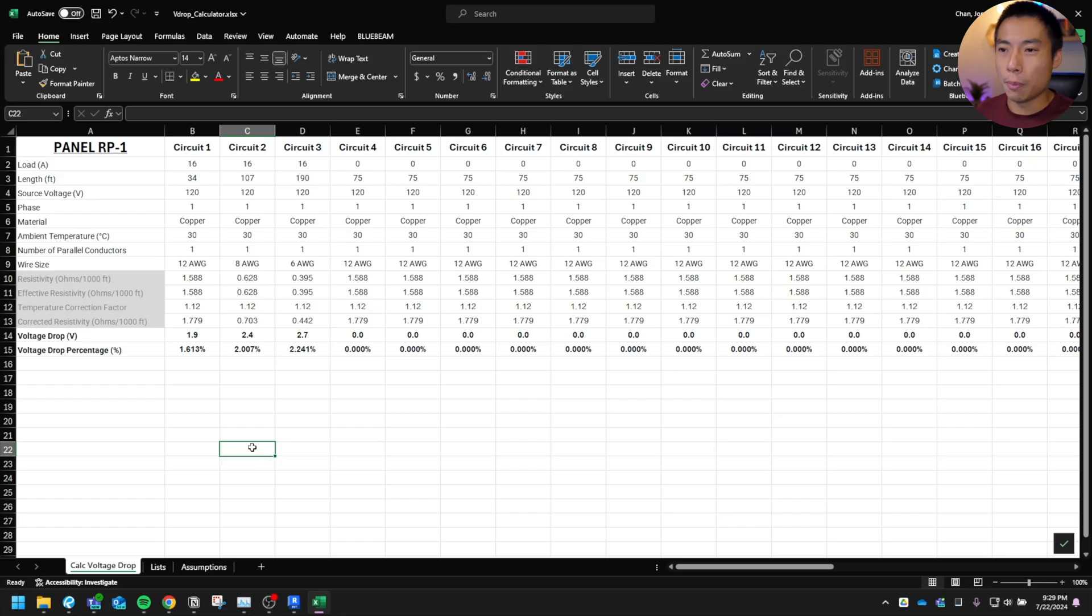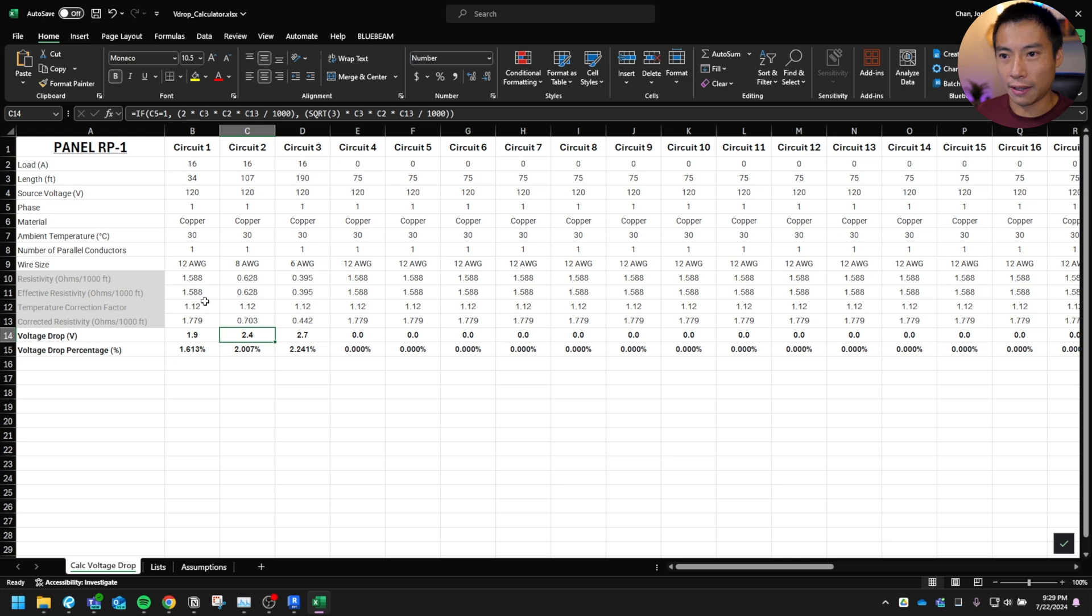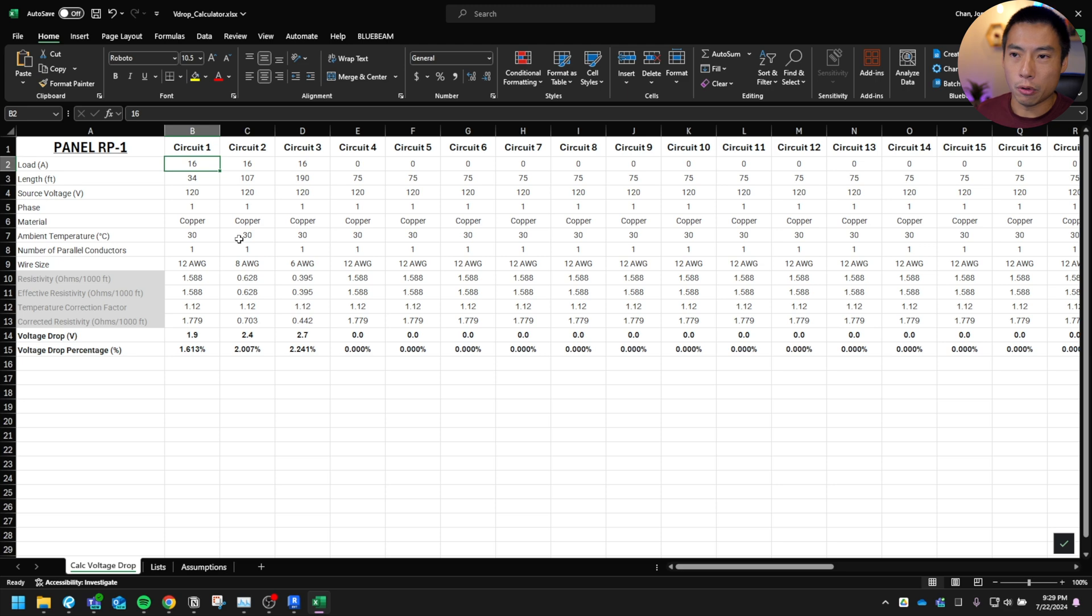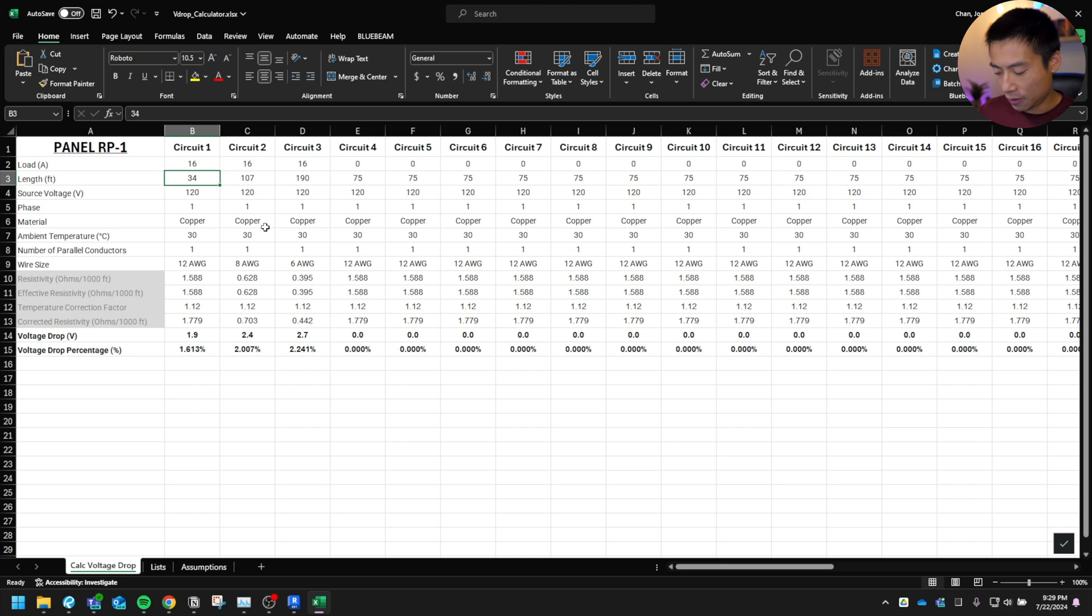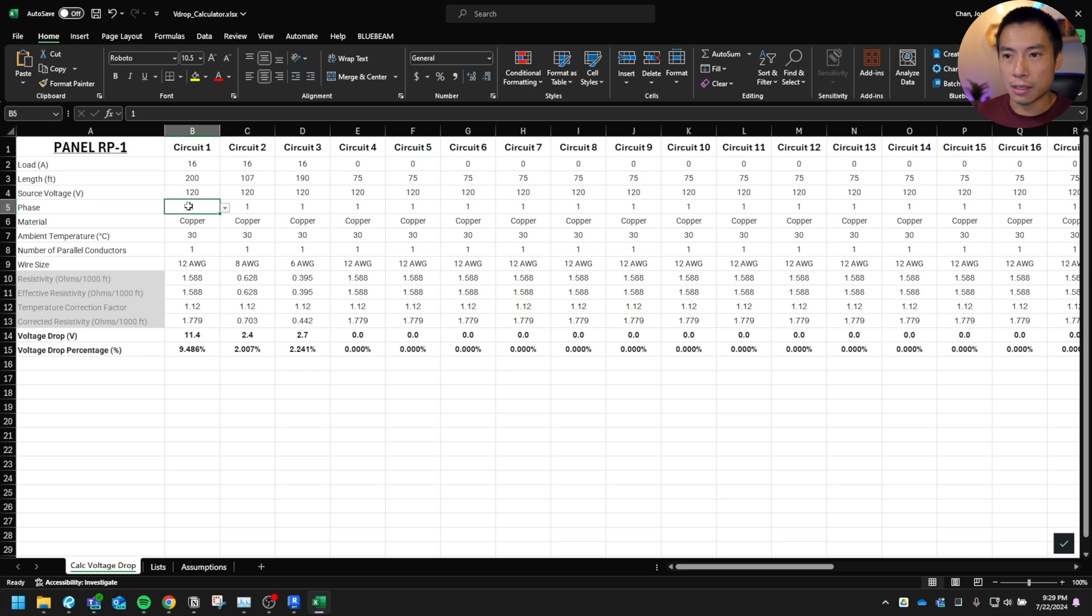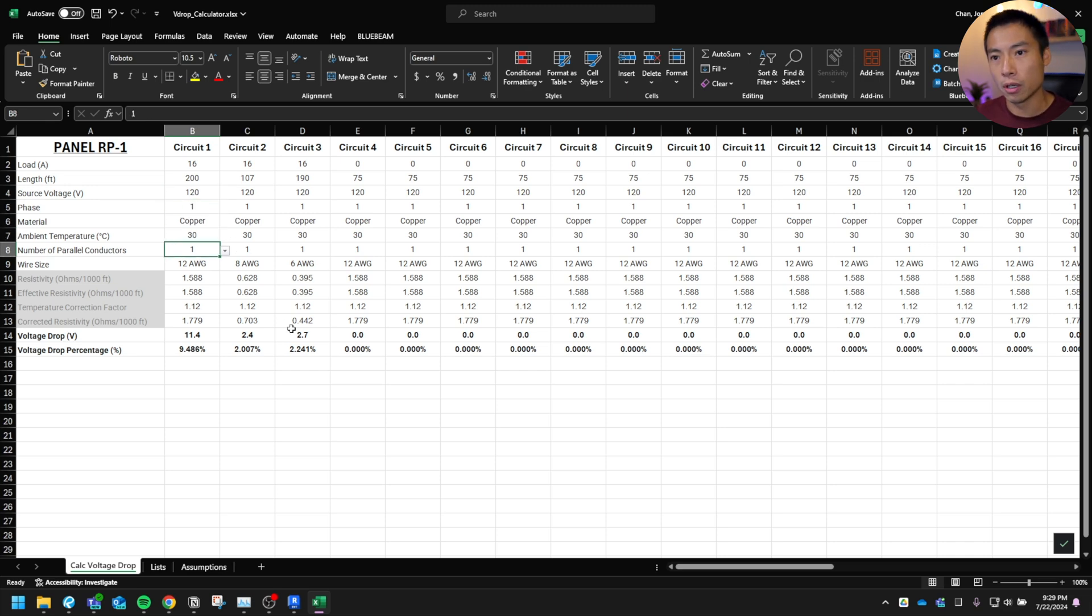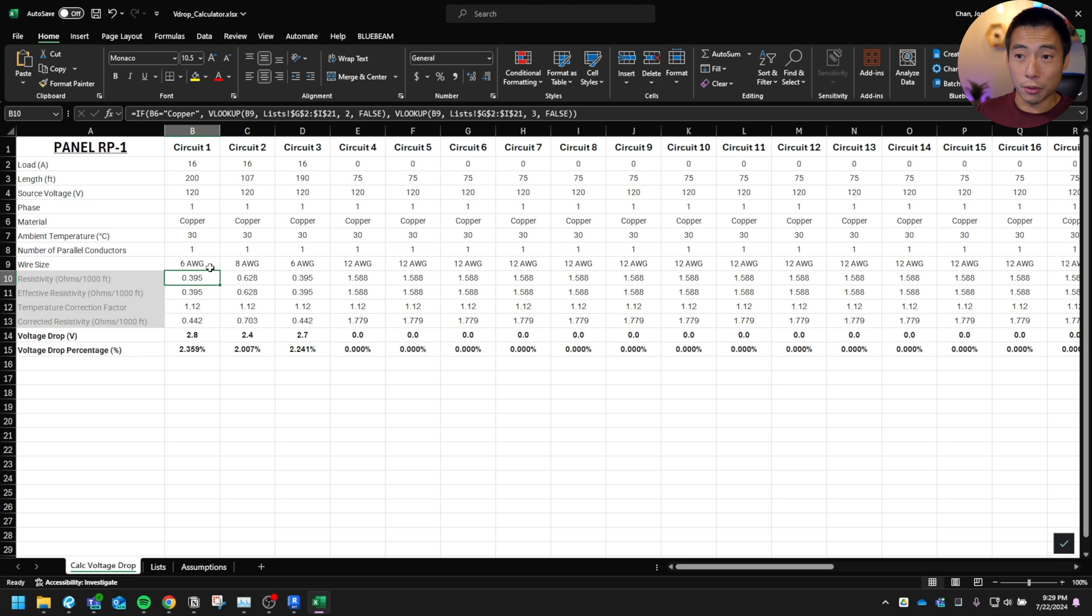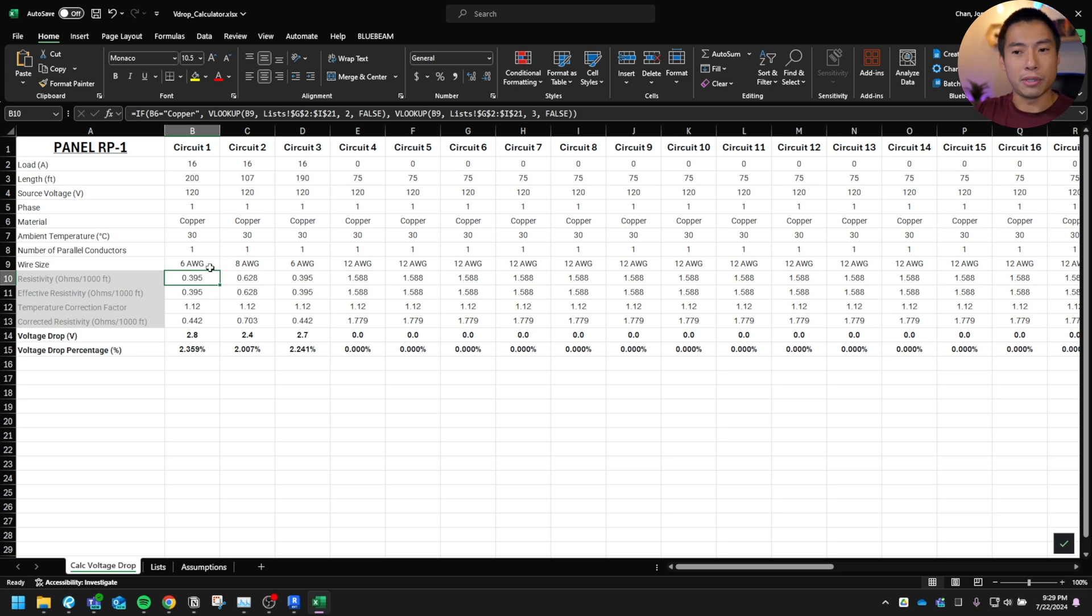So like normally, I would pull up a spreadsheet like this and this spreadsheet, I would punch in the load. So I would say I'm going to pull 80% of the circuit, so 16 amps. And then my distance was like 200 feet or something. And then with my voltage at 120 volts, I select my phase, my copper type, my ambient temperature. And then over here, I start playing with my numbers and it turns out I needed a number six to be able to keep under my 3% voltage drop.